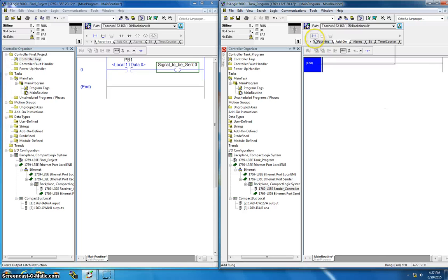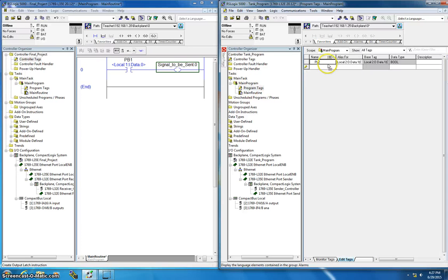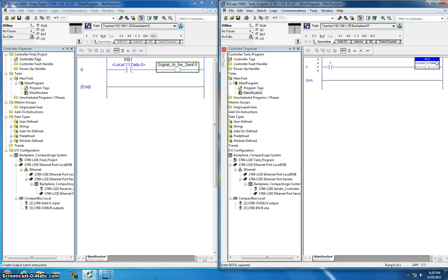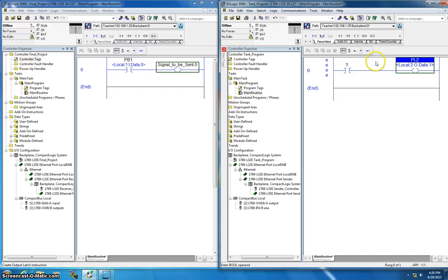I add the 'signal to be sent' tag to the rung. Since it's a DINT and I only need to send one bit, I identify the specific bit inside the DINT — I double-click, click the arrow down, select 'signal to be sent' bit zero, and hit Enter. It now reads 'signal to be sent.0'. I also add a PL2 output (my pilot light) as local data. This will be my consumer tag — it will consume whatever value my producer tag is at.